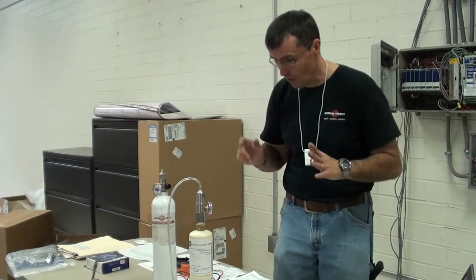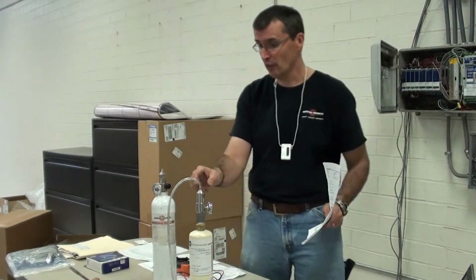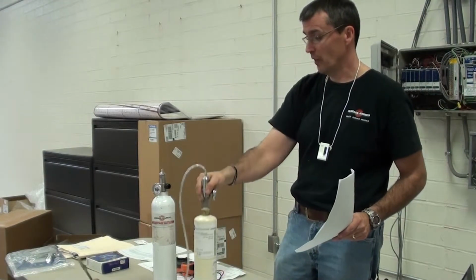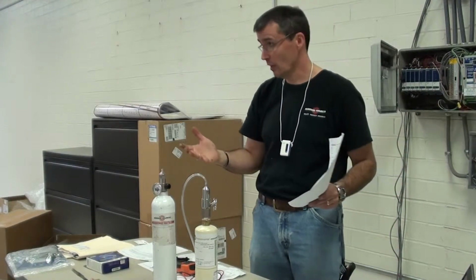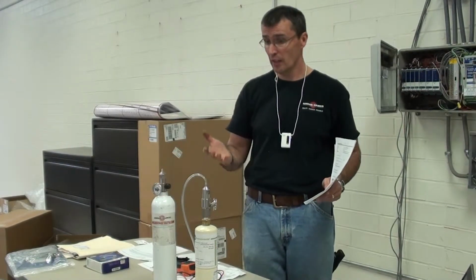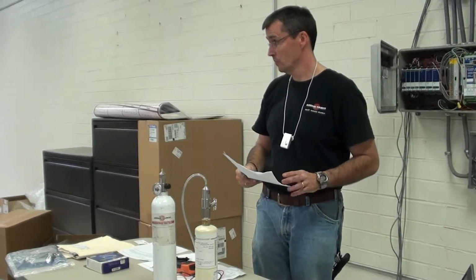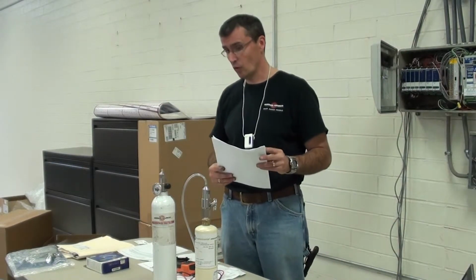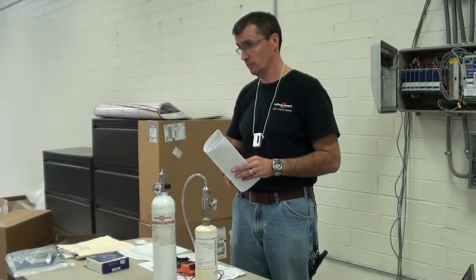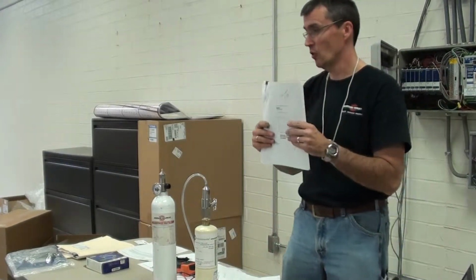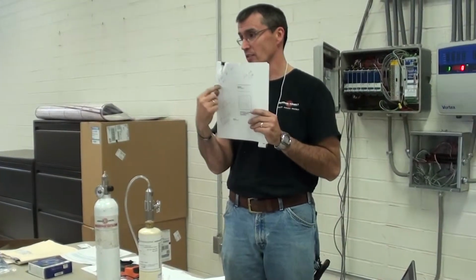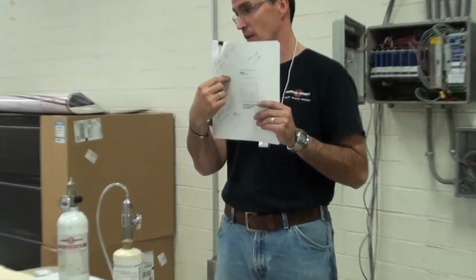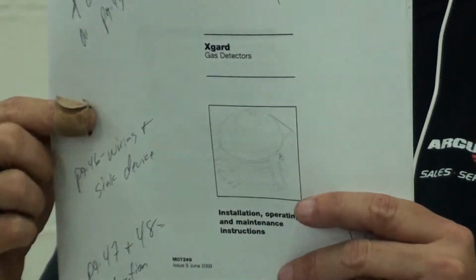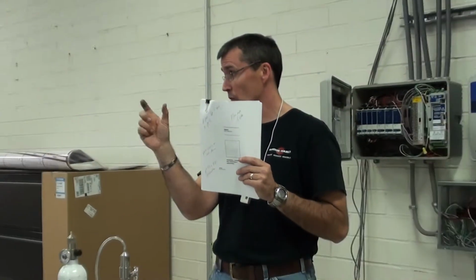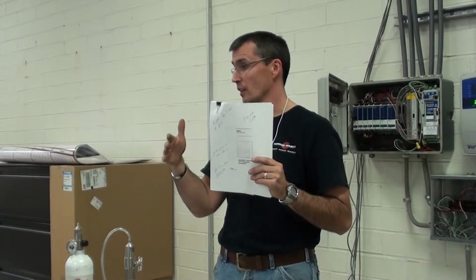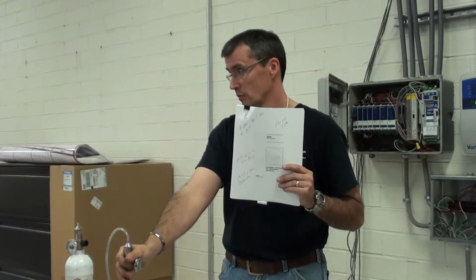Okay? So there's an algorithmic formula that you use to calculate your millivolt output depending on what gas you're using. In our example, and what you guys would probably use, is set up for 35% LEL. Okay? And 35% LEL represents 96 millivolts. There is a formula in the Xgard that basically takes your calibration gas, divides it by the range of the sensor, multiplies it by 40, and then adds 40 to it or something like that. So you use that formula that's in there to calculate the millivolt output depending on what gas you're using. Make sense? Yeah.